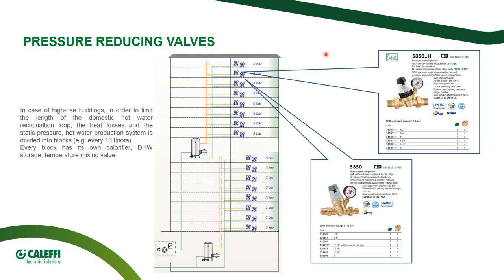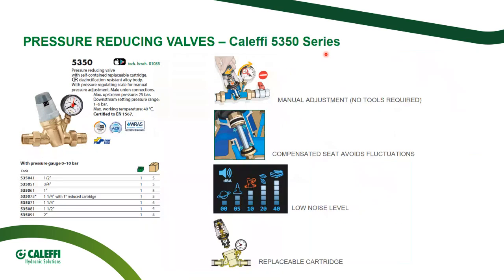So pressure reducing valves can have several features, and we would like to give you some tips about what to look for when we consider them. First of all, they have to be stable and reliable. So Caleffi devices, we would like to show you the 5350 pressure reducing valves. They have a compensated seat. This will allow the valve to be stable in regulation despite the upstream system pressure fluctuation. It is very important for a correct, stable, and safe regulation.